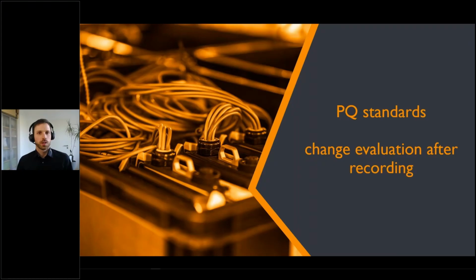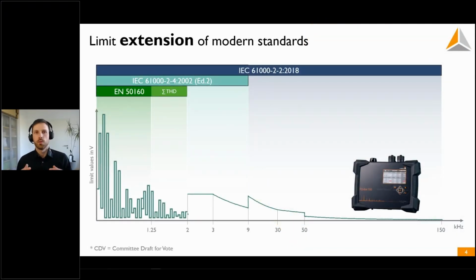So first, I'm going to start with the PQ standards and how to change the evaluation method after the recording. First of all, more and more standards worldwide extend their limit range into higher frequencies. So high frequencies, not the 50 hertz and 60 hertz. That doesn't mean the nominal frequency in our electricity grid, but the interference frequency. So we are talking about harmonics and supraharmonics. And the first standard that closed the gap between 9 and 150 kilohertz was the IEC 61000-2-2 standard back in 2018. So this was the first one that came up with limit values up to 150 kilohertz.